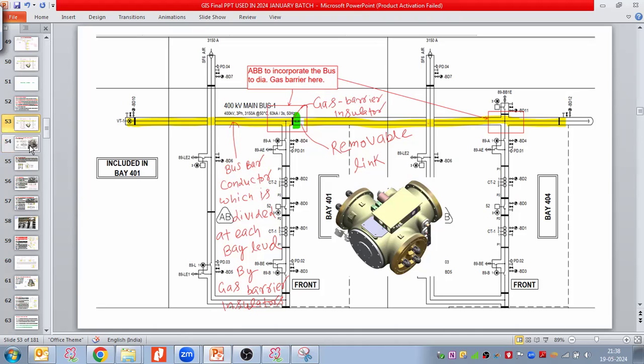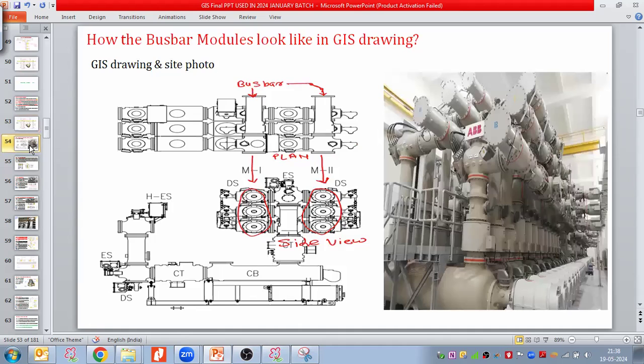So now let us see how the bus bar modules look in the drawing and at the site as well. When you are working as a design engineer, you will get the GIS drawing from the GIS manufacturer. So how will you identify which portion in the GIS drawing is representing the bus bar module? See here, they have given the plan view and section view. The GIS supplier has submitted this drawing. As a design engineer, you have to review and approve this drawing.